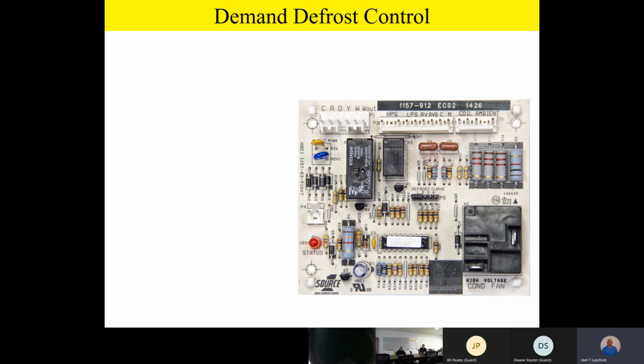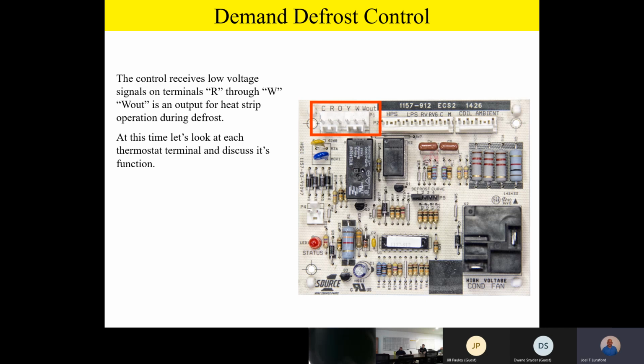So as we take a look at our demand defrost control a little bit closer, we see that we're going to have a low voltage harness. Now, this low voltage harness is where we're going to receive low voltage signals on terminals R through W. It should be noted, W out is an output for the heat strip operation or the auxiliary heat during defrost operation. So we're going to blow that up a little bit, and let's look at each input and each output. And remember, team, this is going to be a harness plugged on with about a 6 or 8 inch pigtail to make your low voltage wires up from your thermostat and your indoor unit.